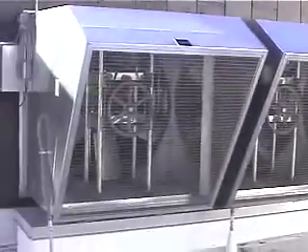Okay. All right. So now we're up on the roof, looking at some of the relief fans, some outdoor air sensors, and that type of stuff. When we came up here, we noticed that one of the relief fans is not running. But aren't they controlled by the static pressure? Yep. So if it doesn't need to be on, it's not going to be on.